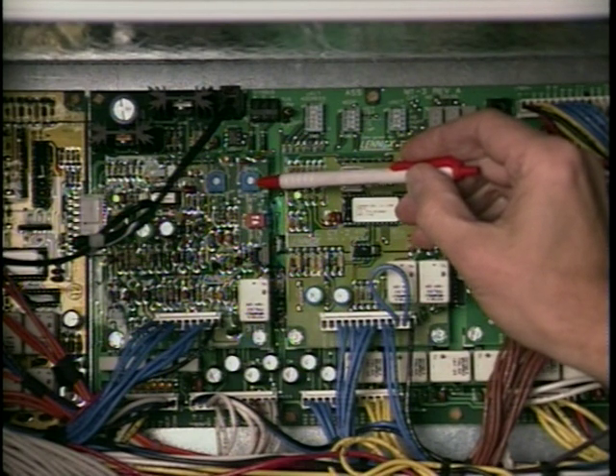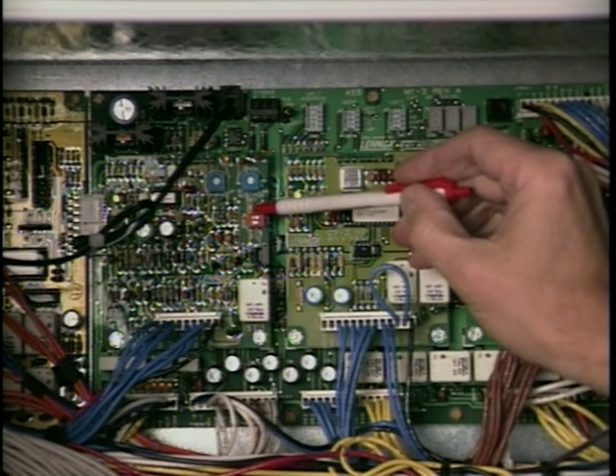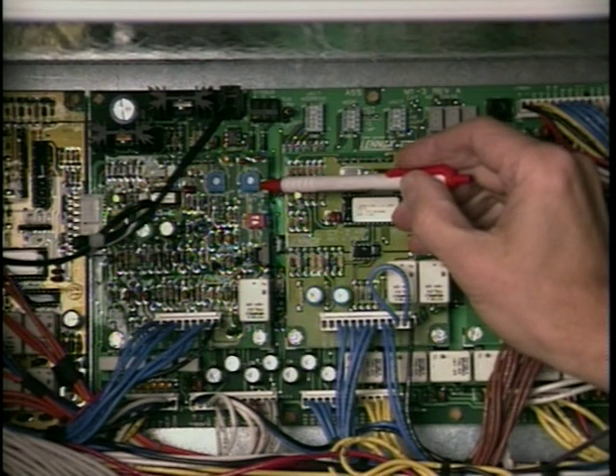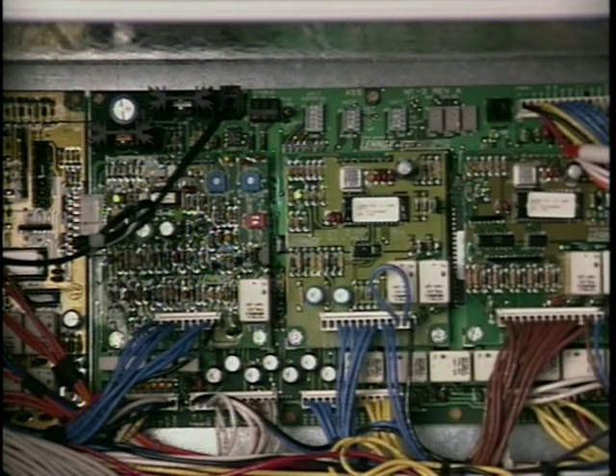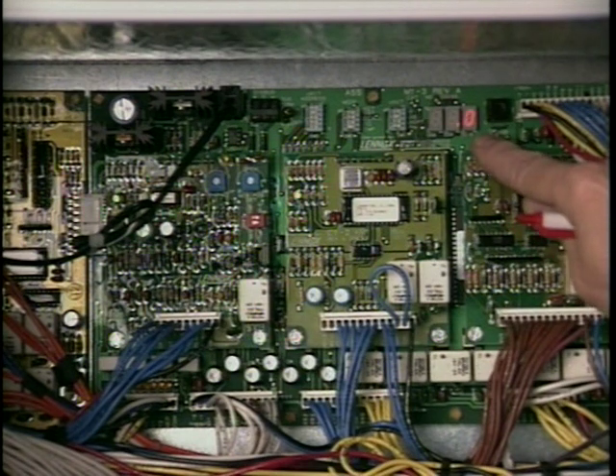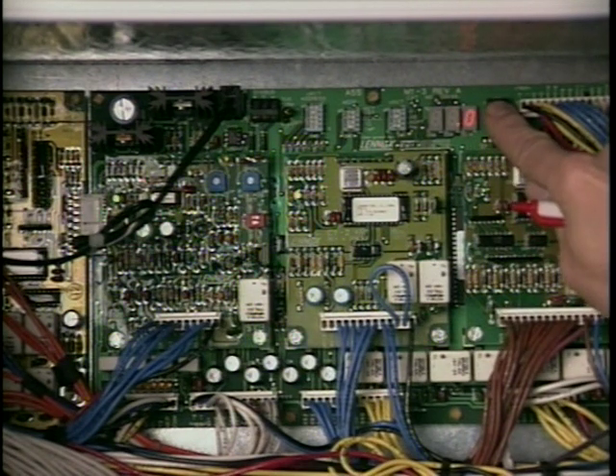You will have to change both the dip switch and 1 potentiometer to complete the checklist, so it is important to display and note the factory settings before proceeding. To display the minimum position setting, place switch 4 on SW2 on. The LED readout should alternate between point 0 and the ambient air temperature. Press the display push button 6 times to advance to point 6. The LED readout will alternate between point 6 and the minimum position setting. Note the minimum position setting.